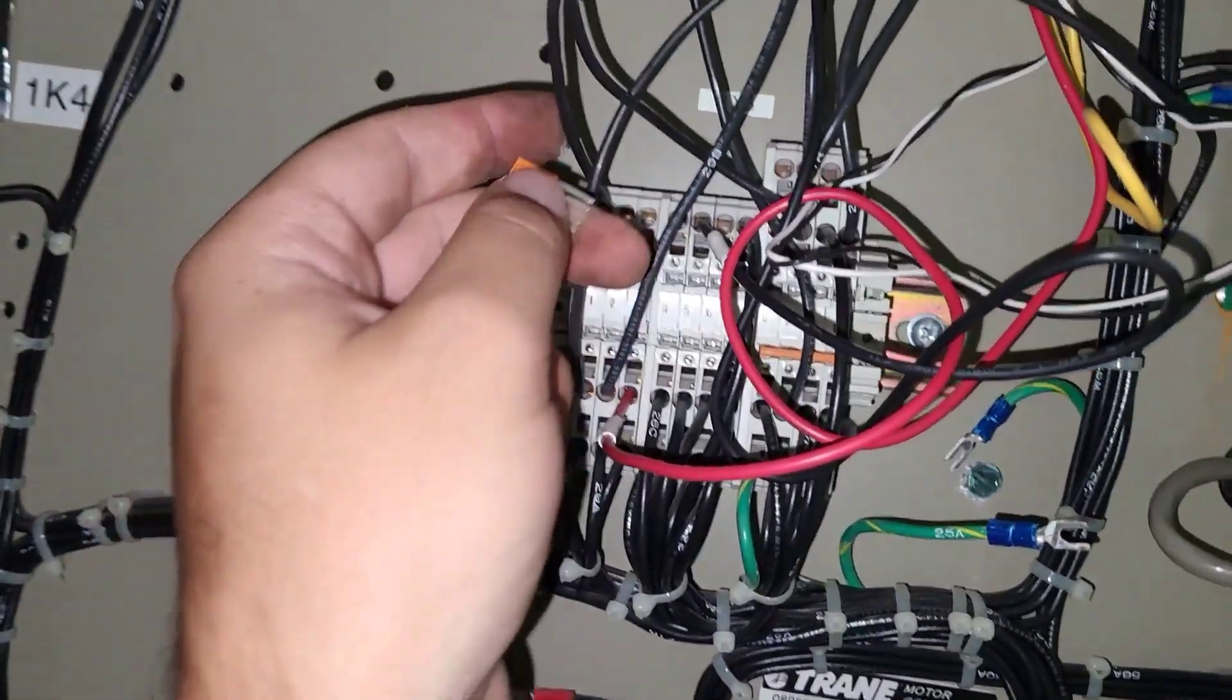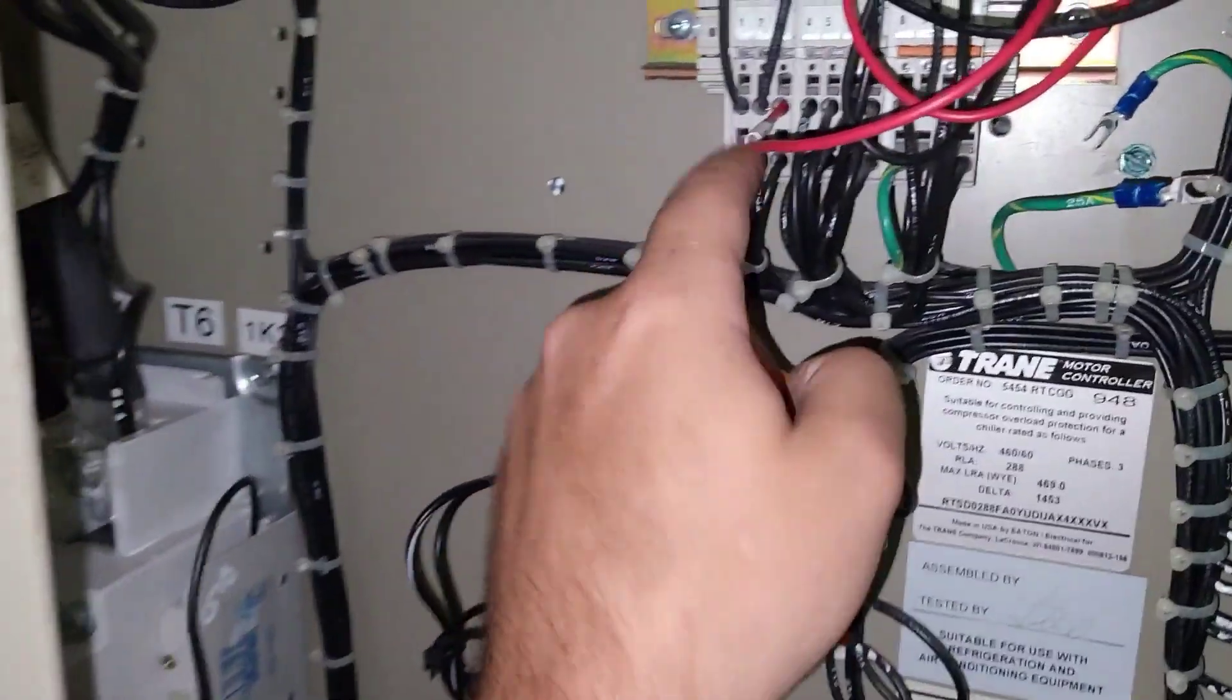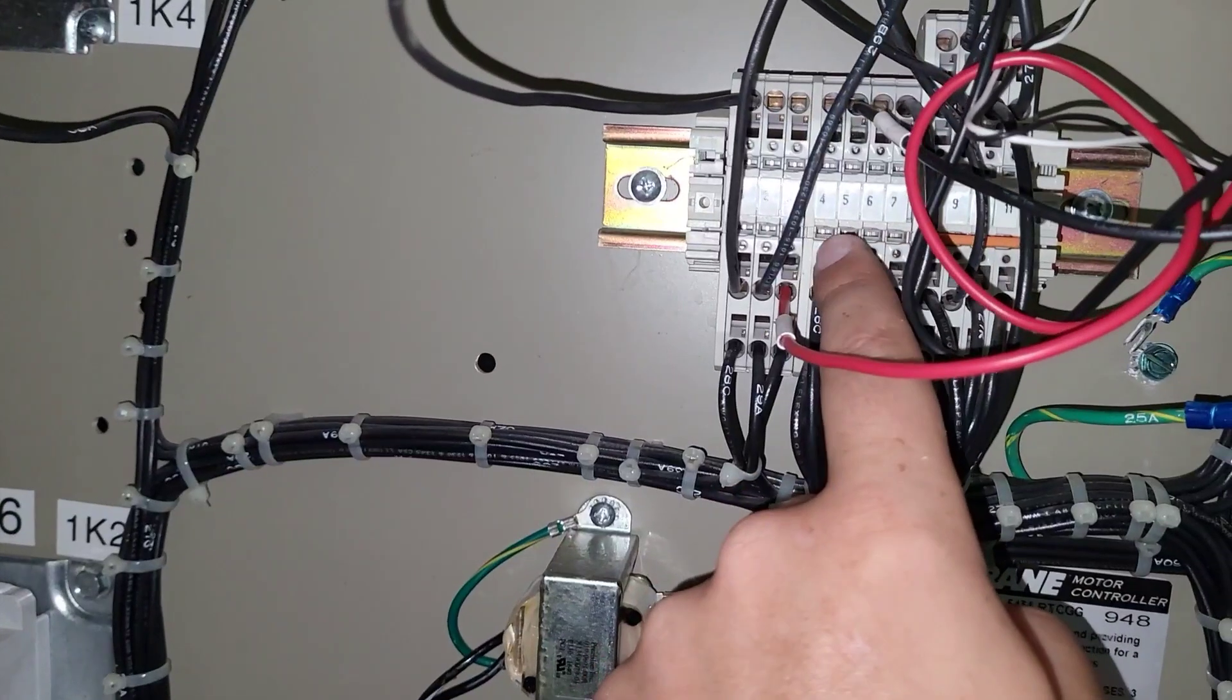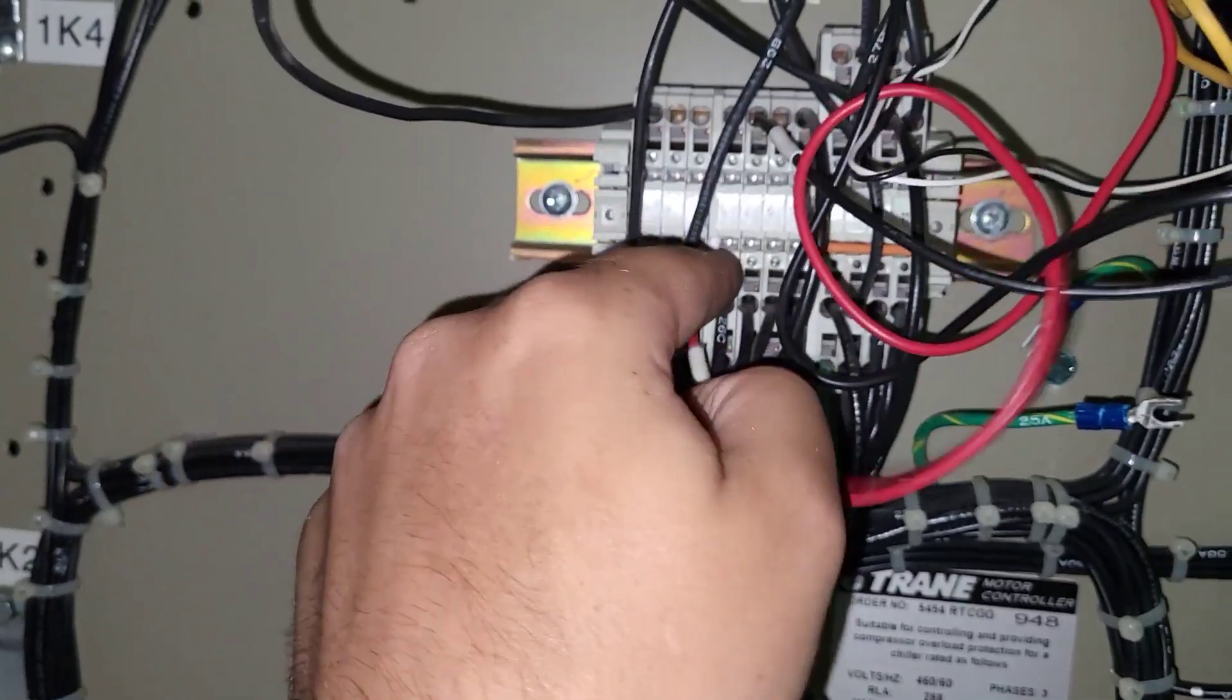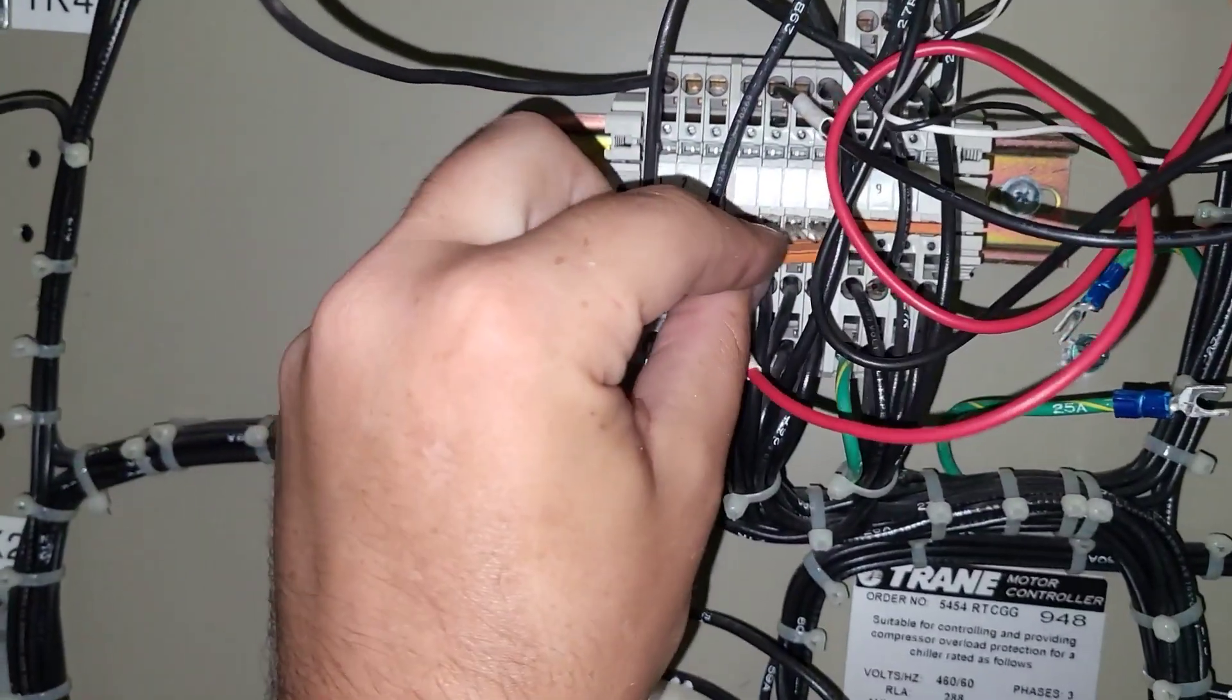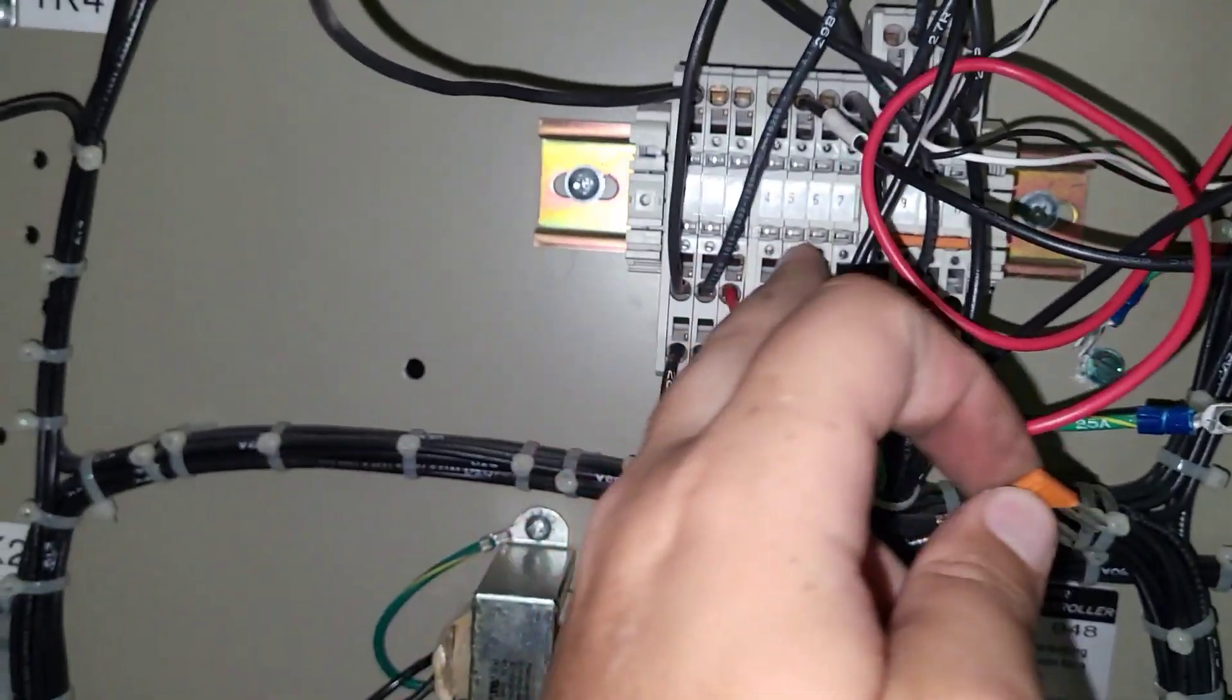I started tracing the oil heaters and was going through the starter auxiliaries. I just kept getting a hit back to ground to the main block here, and ended up tracing it back to these main terminals. There's normally this jumper in place that's going across all of these to tie power back together to all of them.